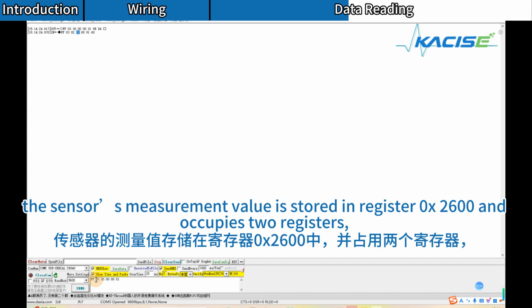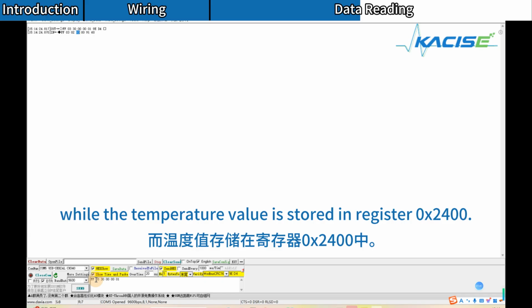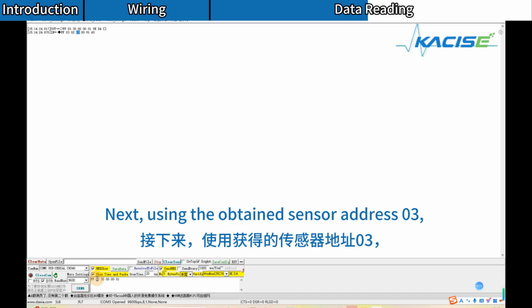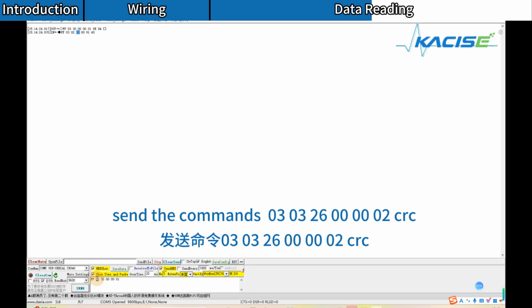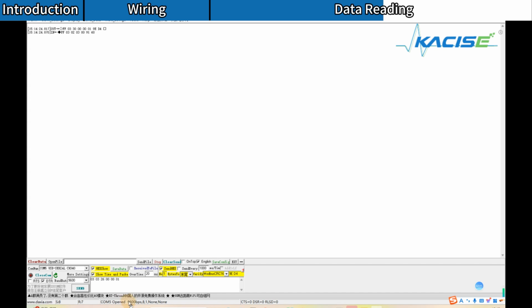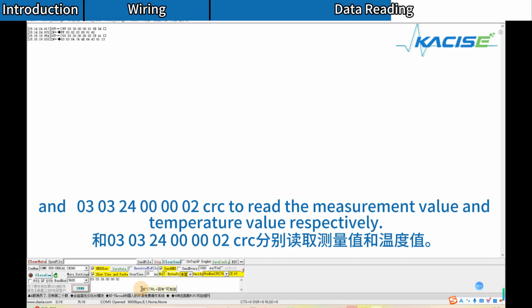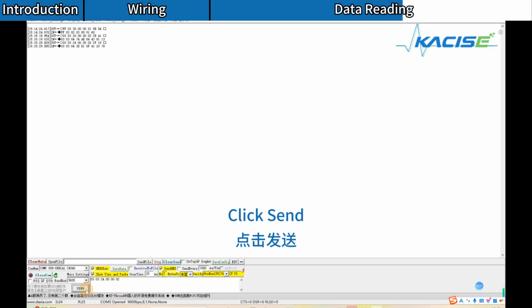According to the manual, the sensor's measurement value is stored in register 0x2600 and occupies 2 registers, while the temperature value is stored in register 0x2400. Next, using the obtained sensor address 03, send the commands 03032600 0002 CRC, and 030324000002 CRC to read the measurement value and temperature value respectively. Click Send.